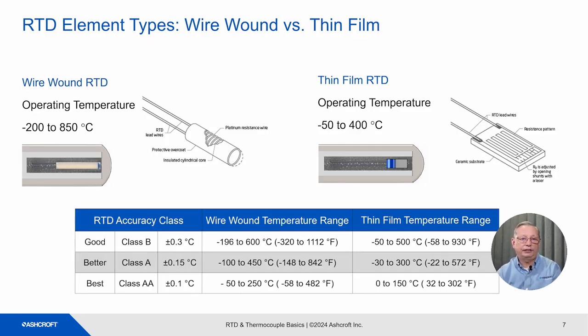The accuracy class of RTD depends on the type of RTD and the temperature range being measured. Class B is good accuracy, plus or minus 0.3 degrees C over the widest temperature range. Class A is a better accuracy at plus or minus 0.15 degrees C over a narrower temperature range, and Class AA is the best accuracy, plus or minus 0.1 degrees C over a very narrow temperature range.